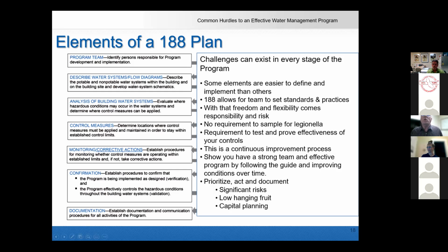Not only is there no requirement for sampling for Legionella, but there's no real standard we get to apply. There's a lot of talk out there that for general system performance, if less than 30% of your samples test positive, you seem to have a healthy system. But that doesn't mean if one sample comes up with a very high colony count in a high risk area, you can ignore it because you're under 30%, right? So it's really a tricky process.